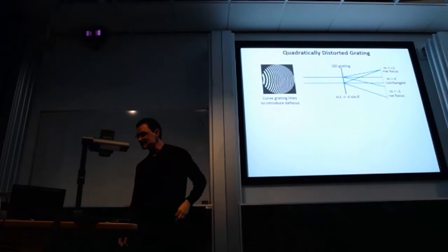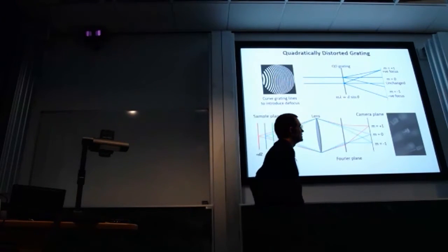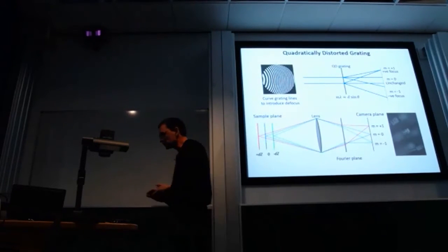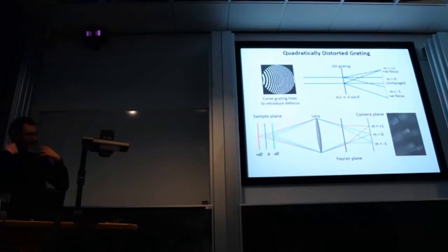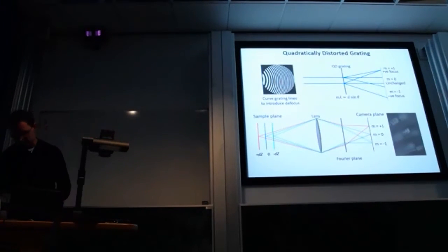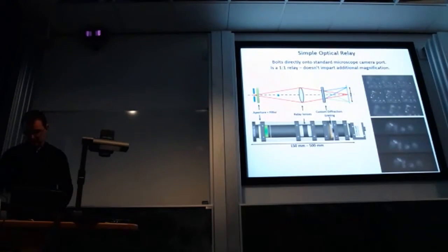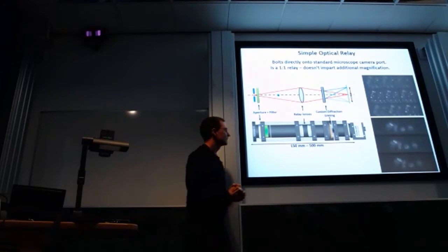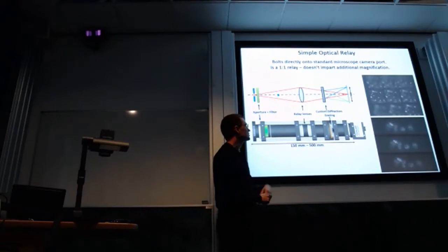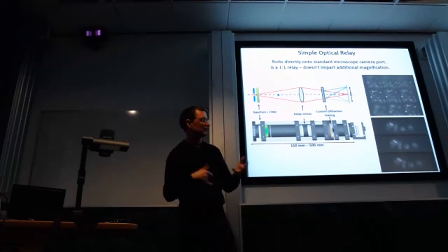If you pair that up with a lens in the right way and put it on your microscope, you can now image different depths inside your sample. And that's what we're trying to do in order to get ultra-high localization precision in all spatial dimensions. The benefit of this is it's a remarkably simple optical system. A very short unit that's about this big, or depending on how you're building it, this big. You can change the gratings very easily, so you can change the distance between the planes. And there's a couple of issues with it, I'll mention some of them.